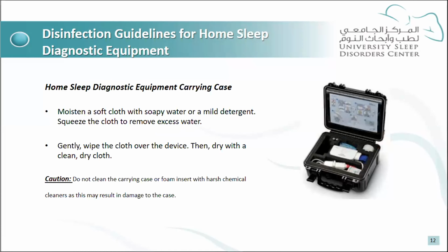Next is the carry case. As I mentioned to you, the carry case is very important. Normally we have the hard carry case for the device, and it can be treated the same as the in-lab equipment, given the design of the equipment itself. So you can use a soft cloth. You can immerse it in mild detergent, squeeze it, then clean the outer area of the carry case, okay? It's very important that you make sure it's dry before using it for the next patient.